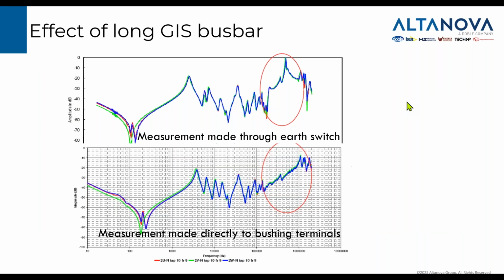Another example, this time of the surrounding area which can influence your measurement. This was measured on a transformer which was normally connected to a GIS busbar. As such, it is not possible to test the transformer when it is connected because there is no access to the terminals. The only thing you can do is to connect to the GIS bar through an earth switch, which was located further away from the transformer, some hundreds of meters away. And this way, get access to the windings. And this is the response that we got in this condition.